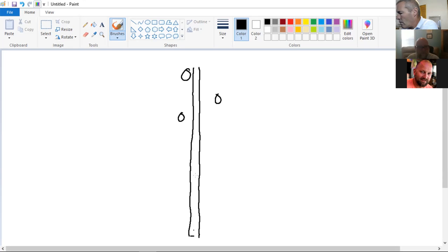You see my screen, right? All right, here's a great example, guys, and you'll be able to see it when we go out to the field on 501. I'm going to draw it like I'm looking down the line: one phase, one phase, one phase, and here's my pole right through the center. Can't remember if there's cross arms or post insulators - put on post. Under that, this is 34 kV. Under that, we have three phases, and this is distribution, 12,470.